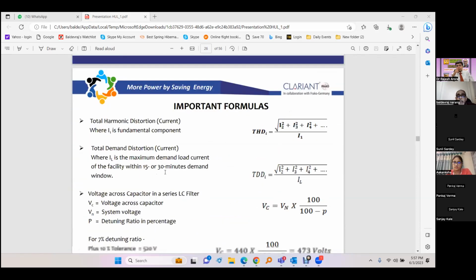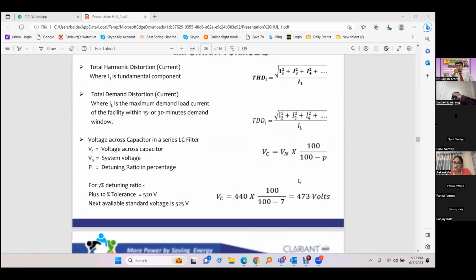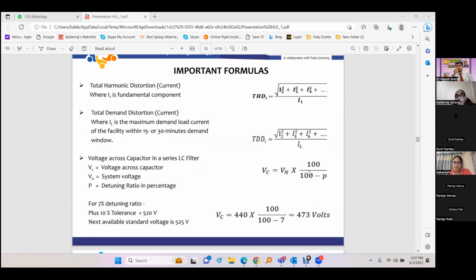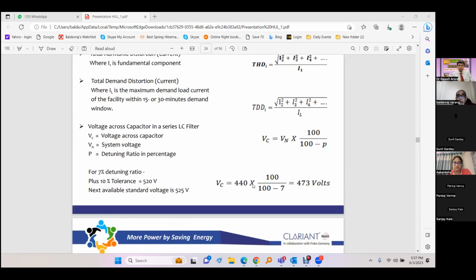And whenever we are connecting a reactor, as I showed earlier, in series with a capacitor for passive filtration, the voltage across the capacitor rises. Suppose we connect a 7% reactor, meaning a 7 kVAR reactor for a 100 kVAR capacitor, the voltage across the capacitor will go up by 7%. So in case we have a 440 volt system and a 7% reactor, which is normally used, the voltage will be around 473, and then we have to consider some voltage tolerance, about 10%. So normally we will be required to use 525 volt capacitors if we are using reactors along with the capacitors.